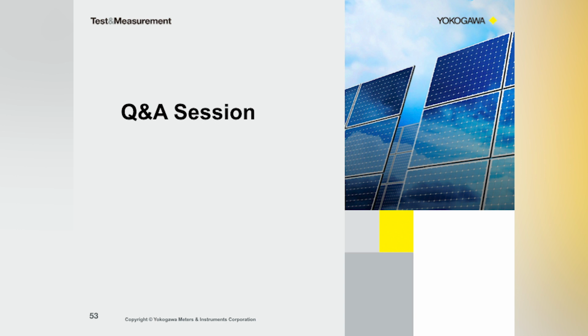Okay. Here's another one. It says, what are the ramifications of setting the CF to 6A? Oh, that's a good one. That's probably a question based on one of our power analyzers. That's a setting that's available to provide a wider effective input range, and if you look through the specifications carefully, you will notice that there is a certain uncertainty additive that you have to take into account when you select that 6A crest factor. So yes, it will affect your uncertainty because you're increasing your effective input range. On the Yokogawa Power Analyzer, we actually specify how much of that uncertainty needs to be added to the original uncertainty. Great, thank you.